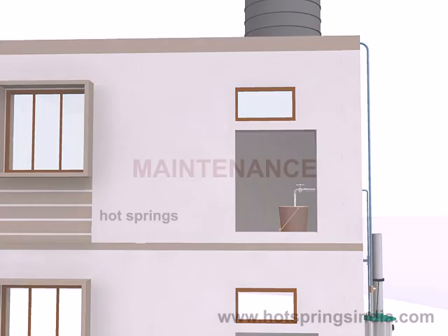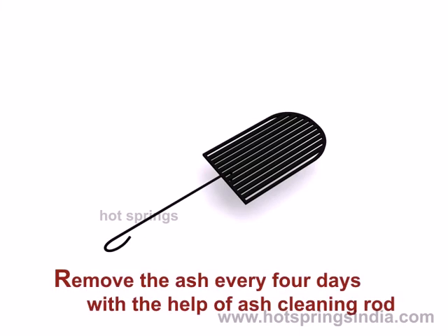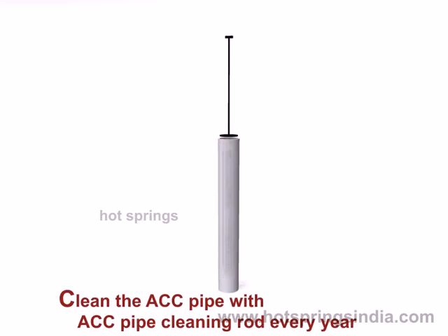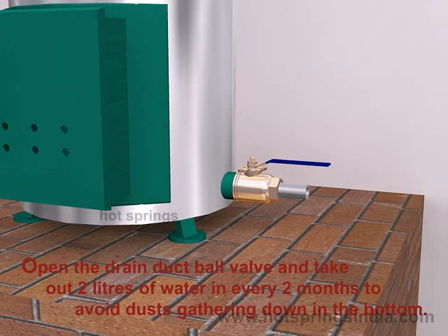Maintenance: remove the ash every four days with the help of the ash cleaning rod. Clean the ACC pipe with the ACC pipe cleaning rod every year. Open the drain duct ball valve and take out two liters of water every two months to avoid dust gathering at the bottom.